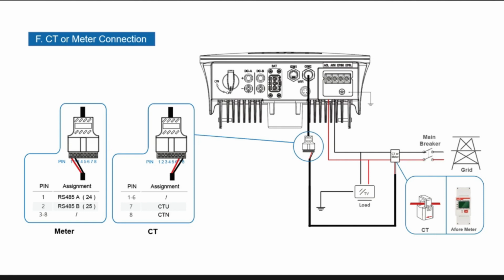After that, you then set the CT or meter, so it knows what it's actually reading and where it's reading from. There's also on that where Don was talking earlier on about self-use, time of use, and the other settings that you can set. There's a setting on the front of here or on the app where you can set it for AC charge and AC charge times, forbid charge, do not discharge times, can all be set on the front of the inverter so you can clearly see what you're doing without having to go over to a computer and then log in to do it that way around. You can get to all of the screens you want to.